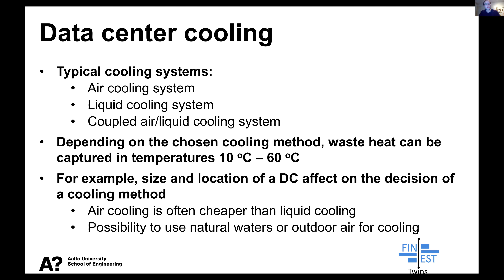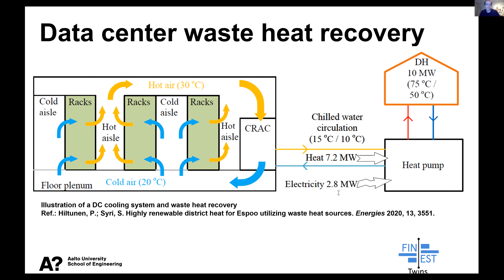And here is an example of how the data center cooling could look. This is an air-cooled system, and the air is led through the server racks where it captures the heat from the servers, and it's circulated back to the computer room air conditioning unit. Here is also added chilled water circulation, which recovers the heat from the CRAC unit, and from that the heat pump raises the heat to a suitable temperature for the district heating network. But this heat pump can also be used directly on the hot cooling air, so this chilled water circulation is not necessarily needed.